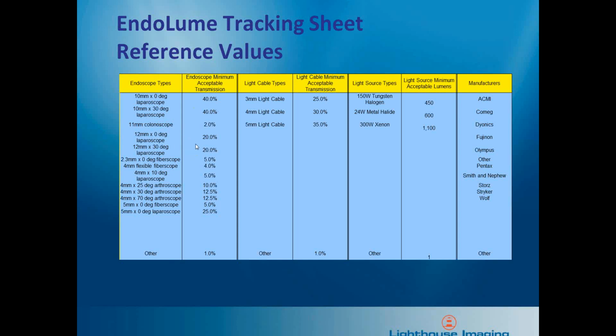This is starting point data: with a 4 millimeter 30-degree arthroscope like I was just looking at, you should get somewhere around 10 or 12% minimum transmission. With a 5 millimeter light cable like I'll be using, you should see about 35% minimum transmission. I don't have a xenon light source here for the demonstration, but a typical minimum light output of a 300 watt xenon light source may be 1100 lumens.